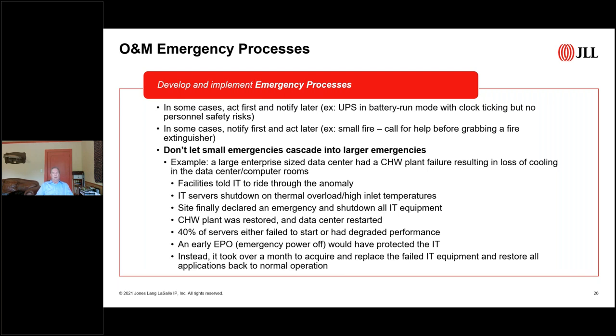The first is that in some cases it's important to act first and notify later. An example would be an uninterruptible power supply that goes into battery run mode. When the batteries run out, the load's going to fail, you're going to have a mission impact. The clock's ticking. But in this situation, there's no personnel risk, no safety risk. So the right action is to immediately try to correct the problem with the UPS and get it done before the battery runs out of life and you have a mission impact.